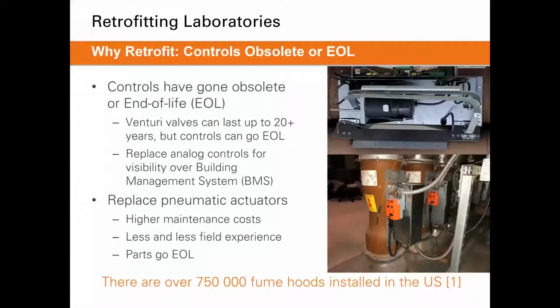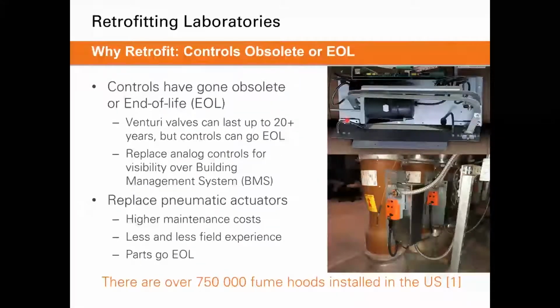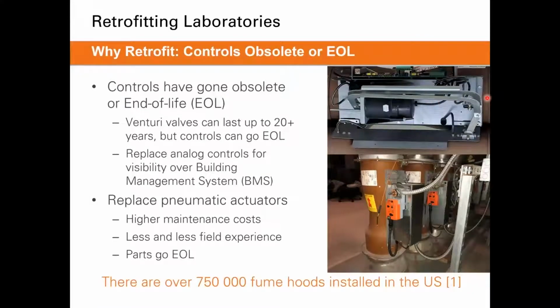Another reason why you may want to consider a retrofit project would be to replace older style pneumatic actuators. And a pneumatic actuator, I have a picture here. It's this black cylinder on the top right. That's a pneumatic actuator. With these come higher maintenance costs, just because of the type of technology. And because they are an older style, there is less and less field experience available out there to maintain these types of actuators. And similarly with the controls, with it being an older style, you may run into the same problem of parts going end of life.